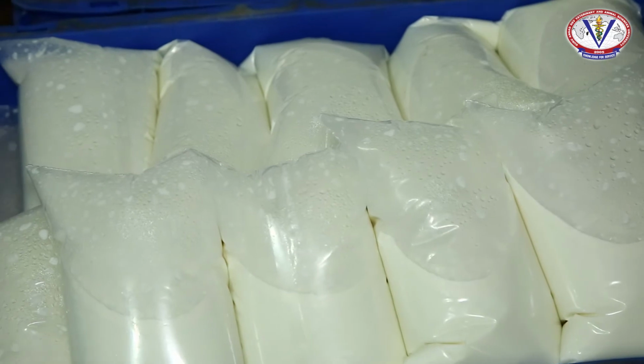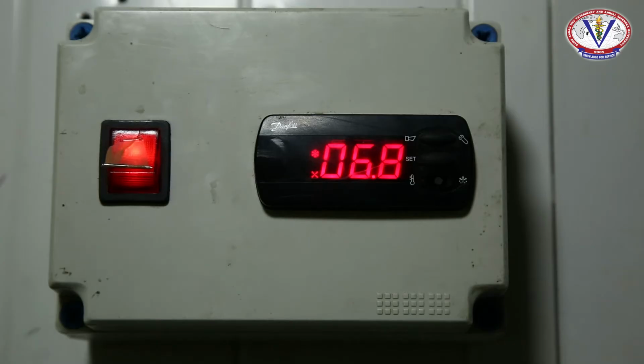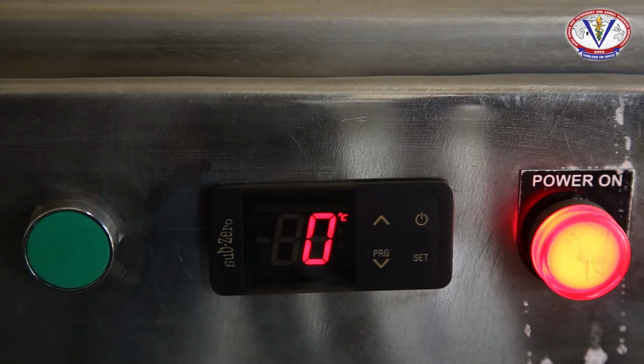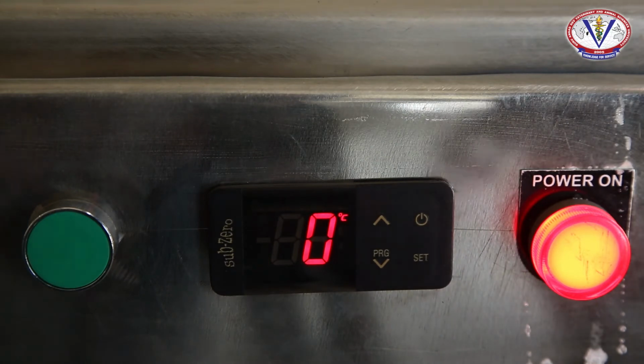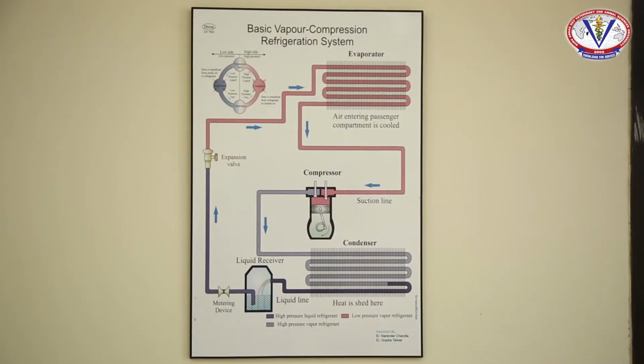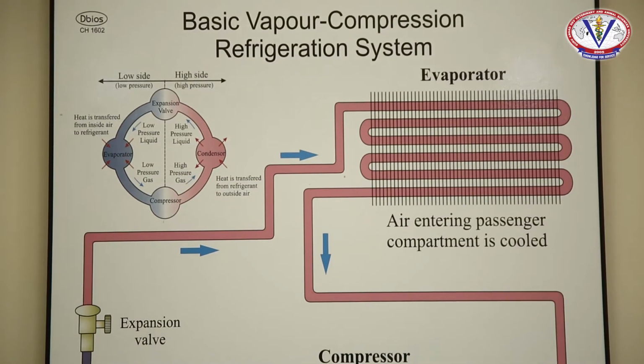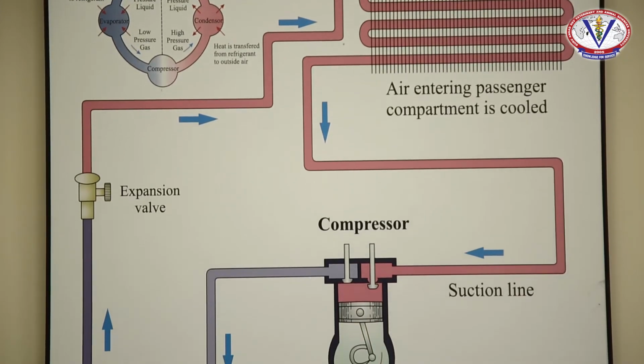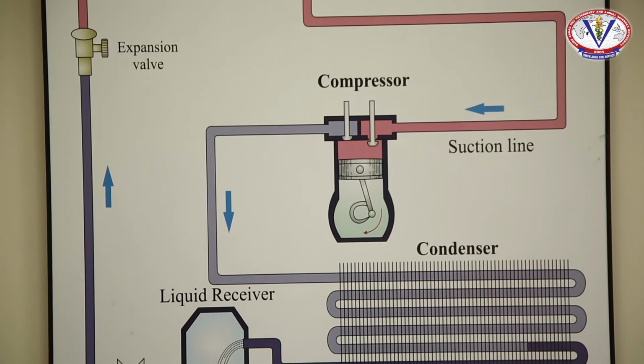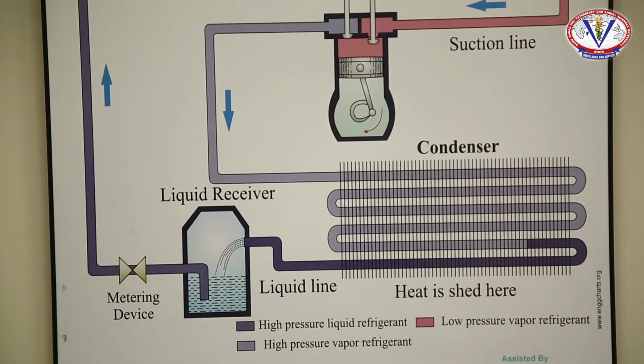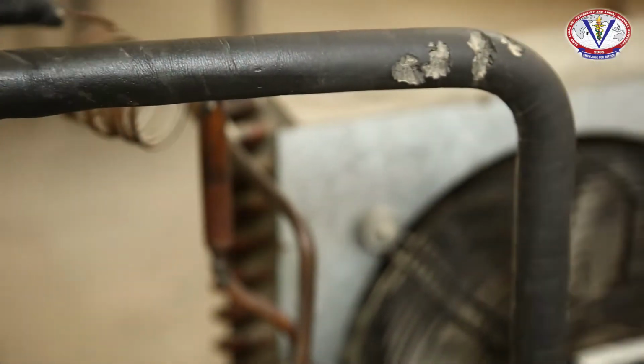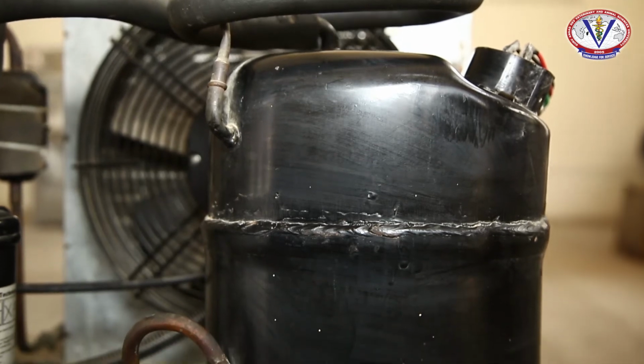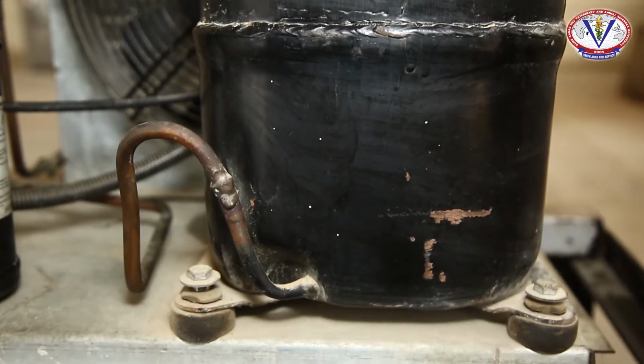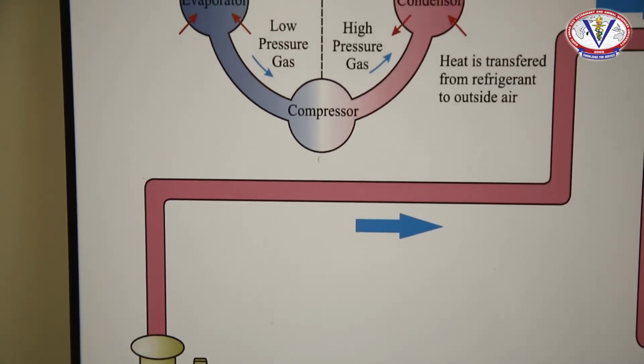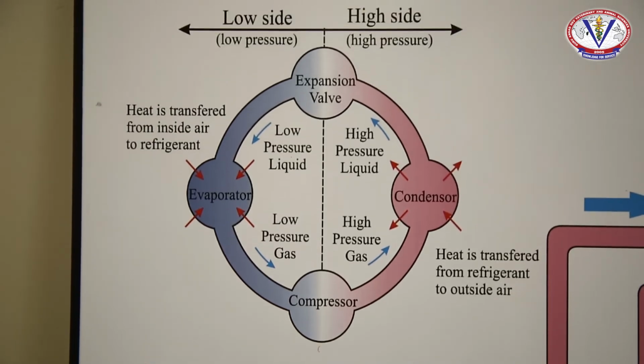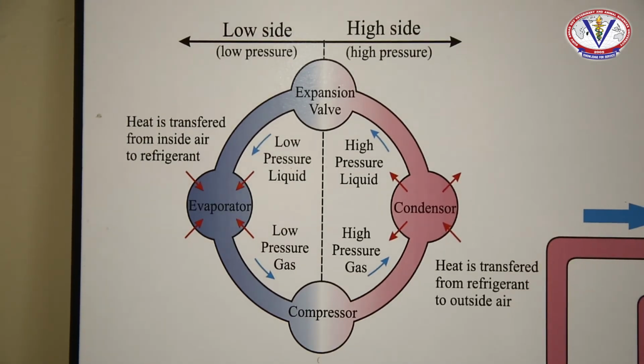Since in dairy plants the temperature range varies considerably, for milk it is on the plus side, and for ice cream and butter it is in the minus or sub-zero temperatures. As we can see, the diagram has been depicted in two color schemes, and these different colors show that the whole system operates between two pressures, low pressure and high pressure. The evaporator operates under low pressure, whereas from the compressor output to the condenser and up to the expansion valve, the whole system operates under high pressure. The same thing has been shown in the side diagram, which shows the low side and the high side.